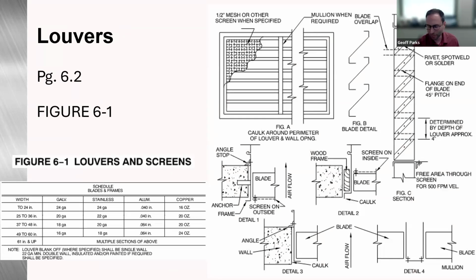So, louvers. This is on page 6.2, Figure 6-1. This covers louvers and screens. For anybody out there that may be fabricating their own louvers, the company I worked for 27 years did a little bit of louver fabrication, especially on smaller projects with smaller louvers. There are some really good details in the Duct Construction Standards that give you your blade and frame gauges based on the width of the louver. Louver blank-offs shall be single wall 22 gauge minimum, double wall insulated or painted if required.